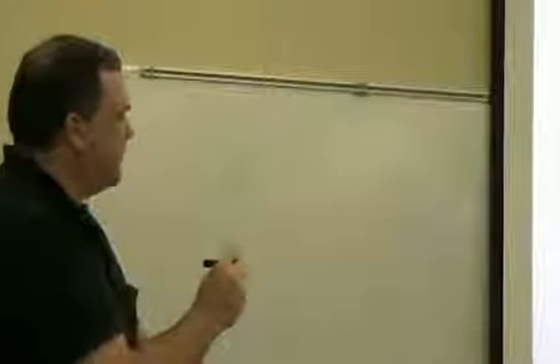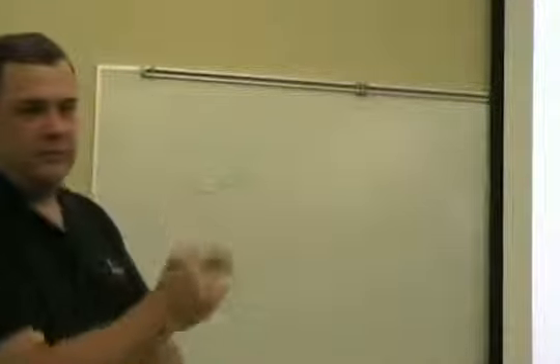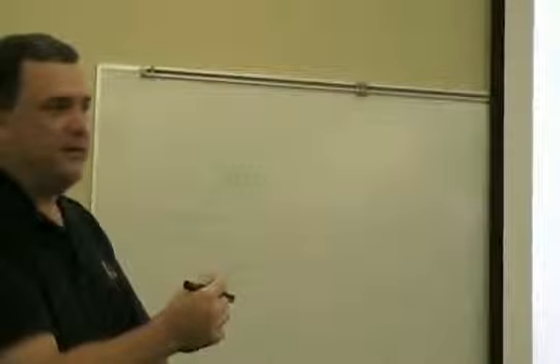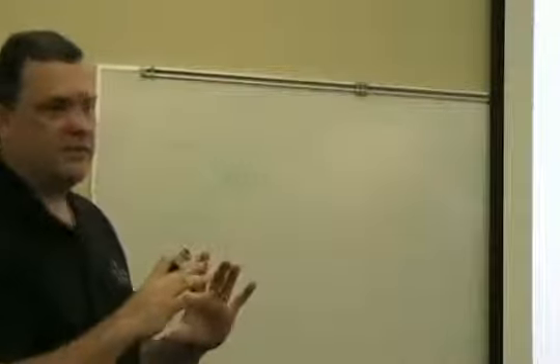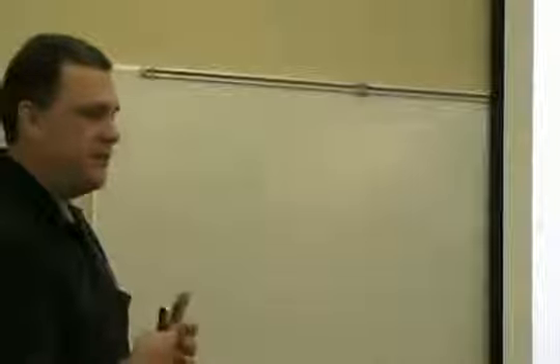The airflow pickups. Every VAV box, almost every one you see in the world today, is going to have some kind of cross-flow sensor that's going to give us an indication of the velocity pressure. Okay? Velocity pressure, we can take that into an equation and calculate the CFM. That's what we need to know in order to make this controller work right.